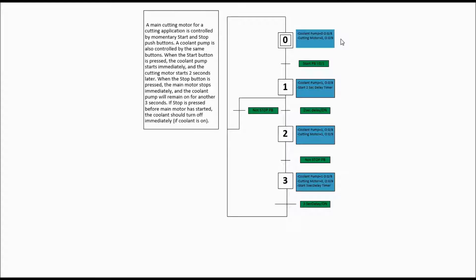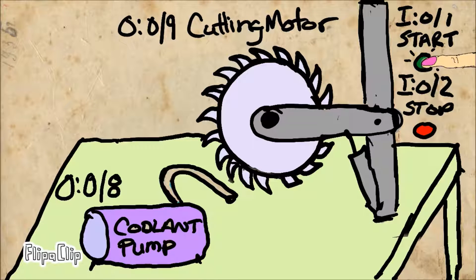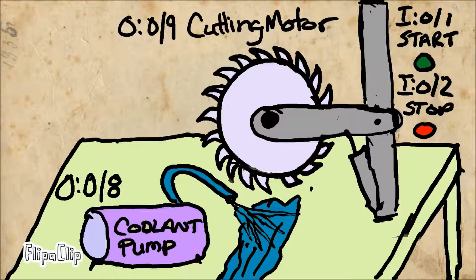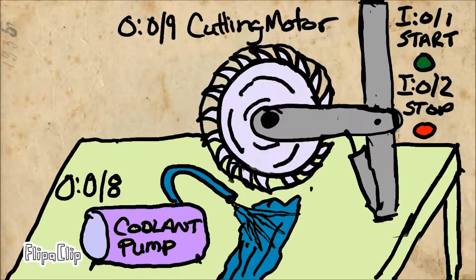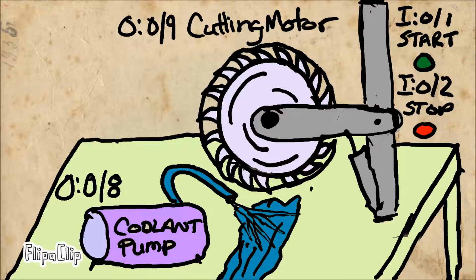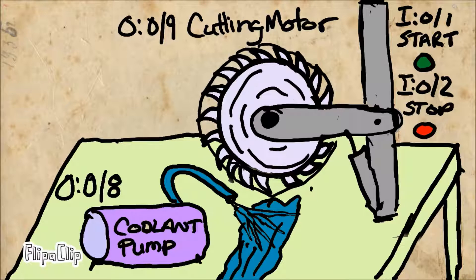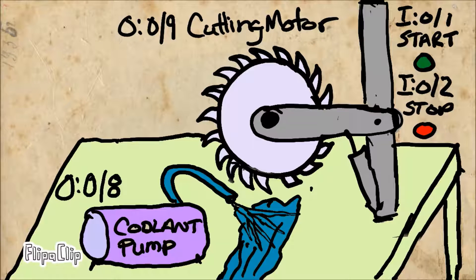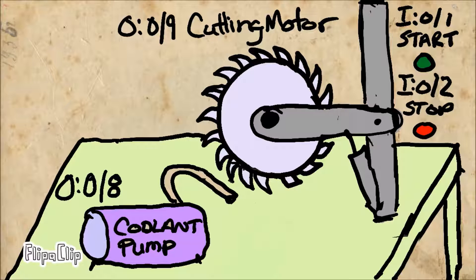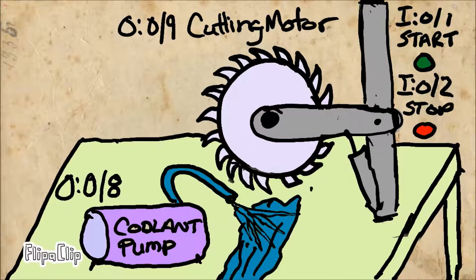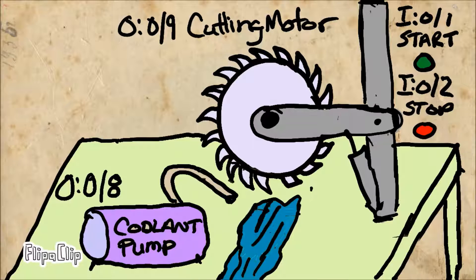Here's a little animation so you get a better idea of what's going to happen. The operator presses the start push button, the coolant starts right away. The motor starts 2 seconds after and continues to run until the operator presses the stop push button. The motor shuts off right away when stop is pressed. 3 seconds later, the coolant pump shuts off. Now let's try it the other way: the operator presses start, the coolant starts, and if the operator presses stop before the motor starts, the coolant shuts off right away.